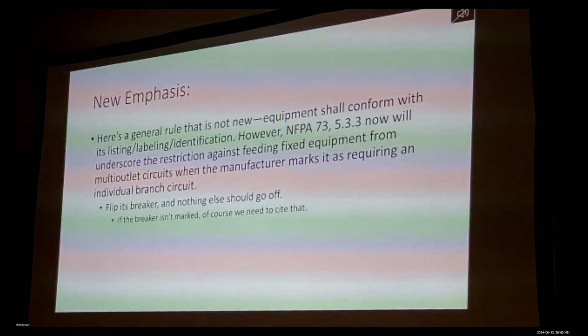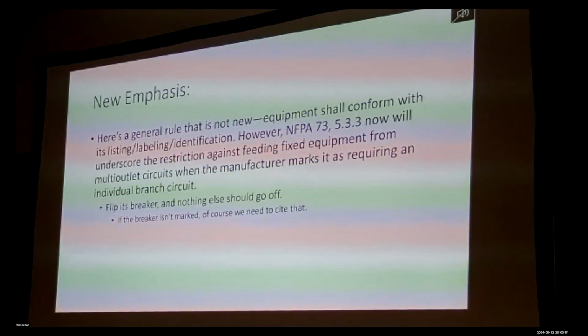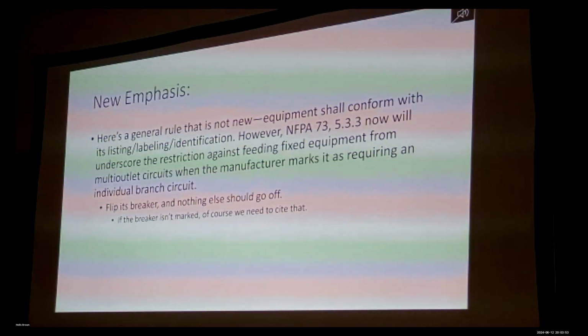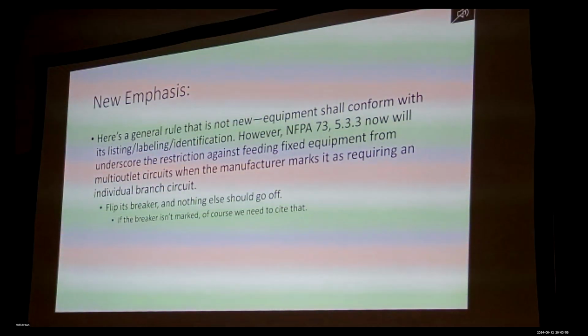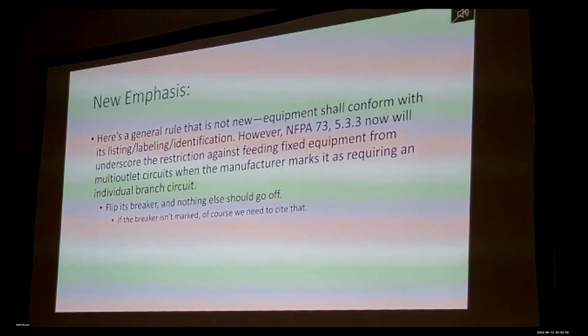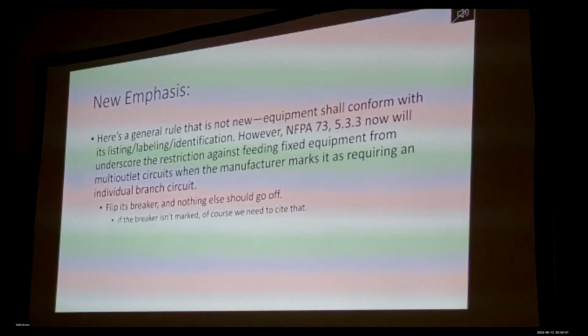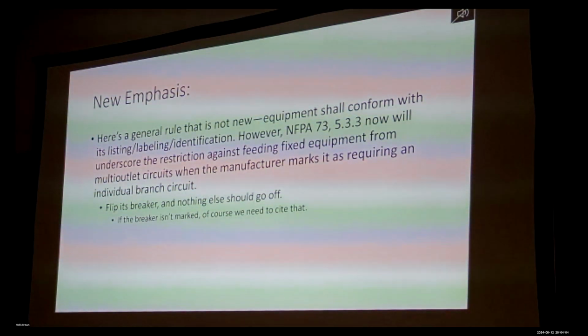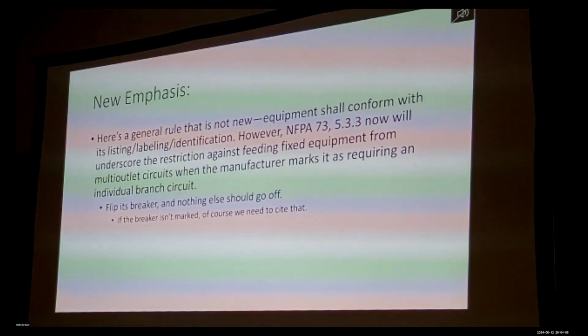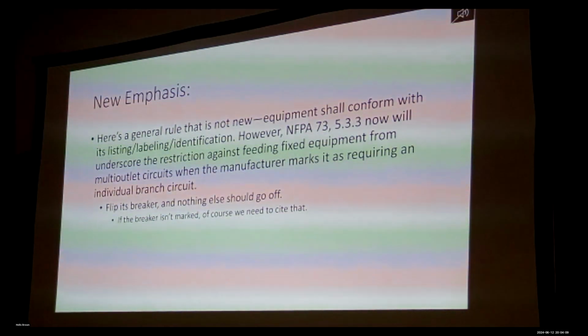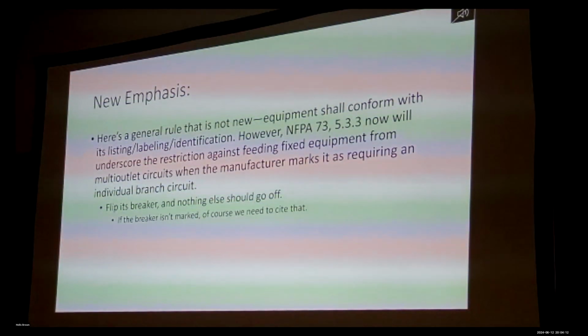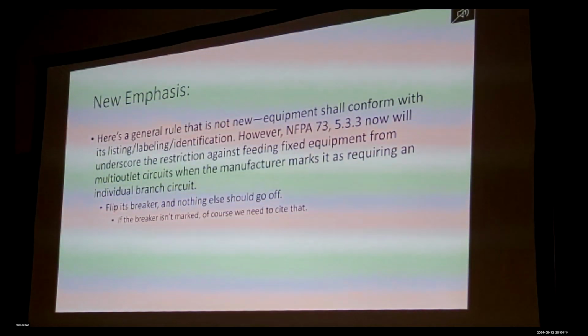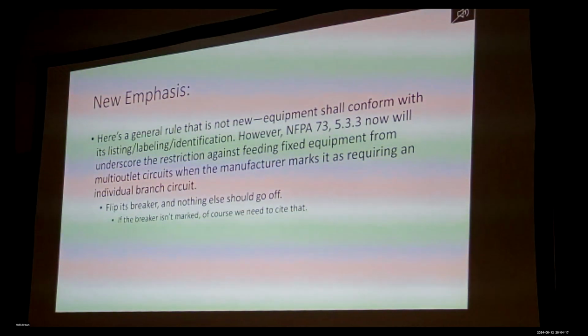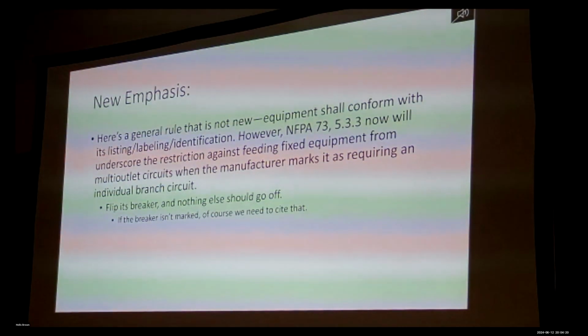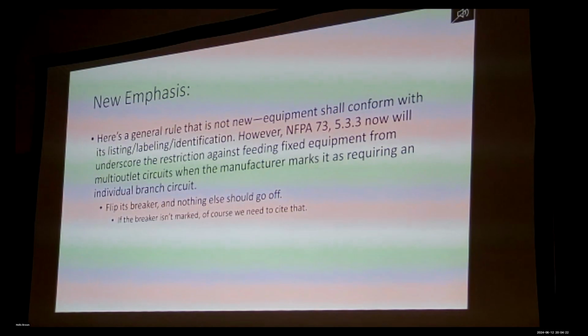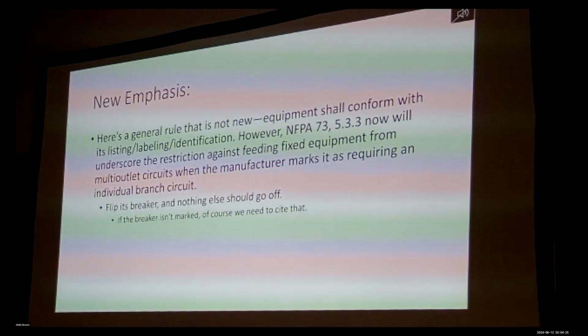So that's new. It matters because it's so hard to figure out whether people are going to overload this circuit, that circuit, or the other circuit. And you can warn them to read the wattage on equipment or use some sense, but if something says give me an individual branch circuit and you see he hasn't gotten one, we're saying kindly, we have a new specification in the rule here: NFPA 73, section 5.3.3.